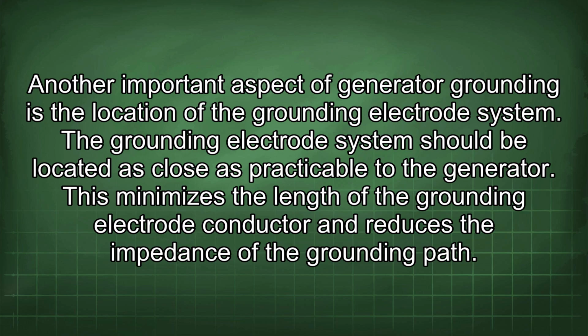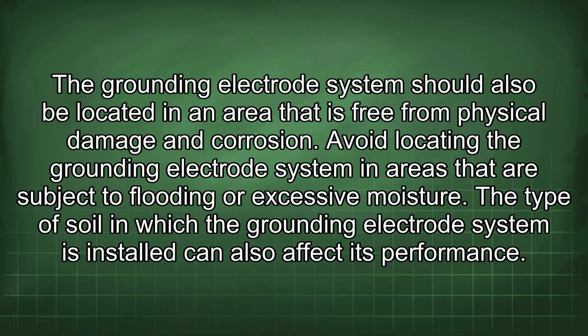Another important aspect of generator grounding is the location of the grounding electrode system. The grounding electrode system should be located as close as practicable to the generator. This minimizes the length of the grounding electrode conductor and reduces the impedance of the grounding path. The grounding electrode system should also be located in an area that is free from physical damage and corrosion. Avoid locating the grounding electrode system in areas that are subject to flooding or excessive moisture.